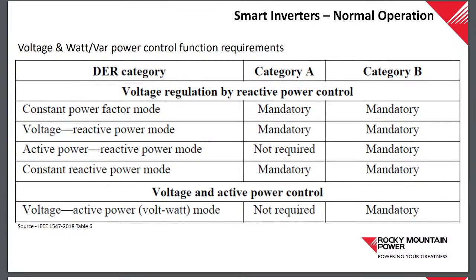A little bit into category A: it's mandatory to have the constant power factor mode, the volt reactive power mode, which you're going to hear a lot called volt-var, and the constant reactive power mode. Category B includes all of category A, but also incorporates the ability to do the volt-watt mode, where you're tracking your voltage but changing the watts.